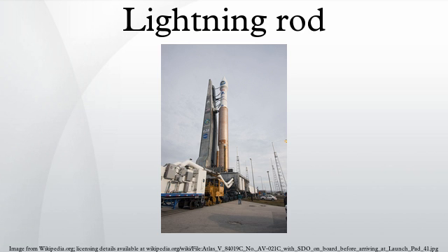These conductors are bonded to earth either through the metal structure of a pole or tower, or by additional ground electrodes installed at regular intervals along the line. As a general rule, overhead power lines with voltages below 50 kV do not have a static conductor, but most lines carrying more than 50 kV do. The ground conductor cable may also support fiber optic cables for data transmission. In some instances, these conductors are insulated from direct bonding with earth and may be used as low-voltage communication lines. If the voltage exceeds a certain threshold, such as during a lightning termination to the conductor, it jumps the insulators and passes to earth. Protection of electrical substations is as varied as lightning rods themselves, and is often proprietary to the electric company.